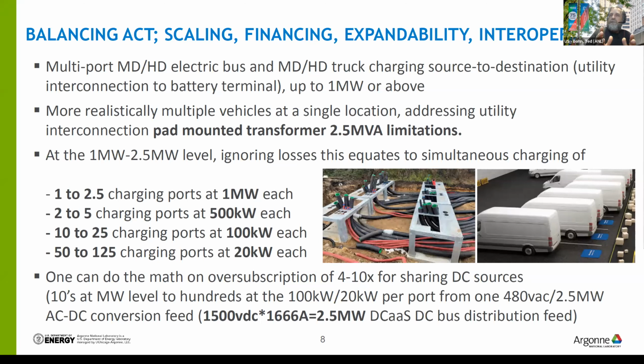Then the delivery vehicles, for instance overnight charging, if I have an 800 kilowatt-hour battery, I can charge 8 hours at 100 kilowatts, and that seems very reasonable. So I can have 10 to 25 100-kilowatt charging vehicles on that one transformer, running it up to the full rating. And of course I can go up to 125 ports if I divide it down to 20 kilowatts, for delivery vehicles that run only 50 miles a day. They can be recharged very slowly and very leisurely, so you can schedule that.